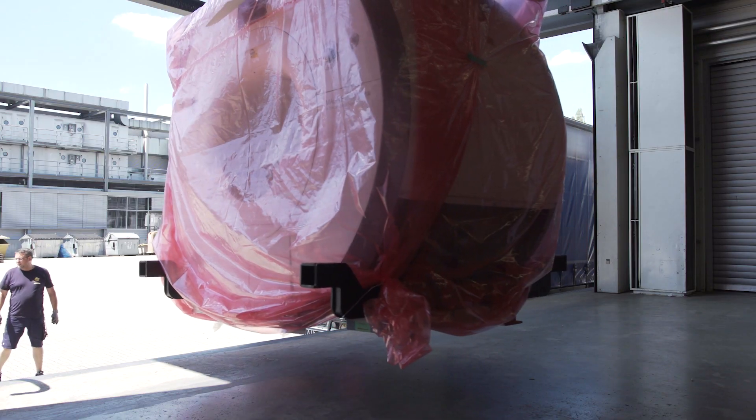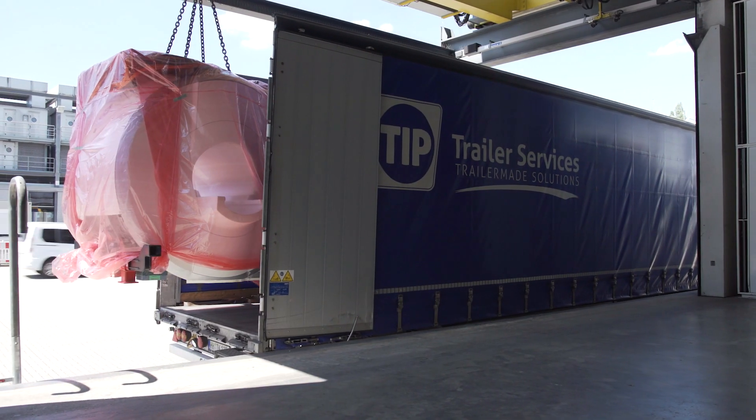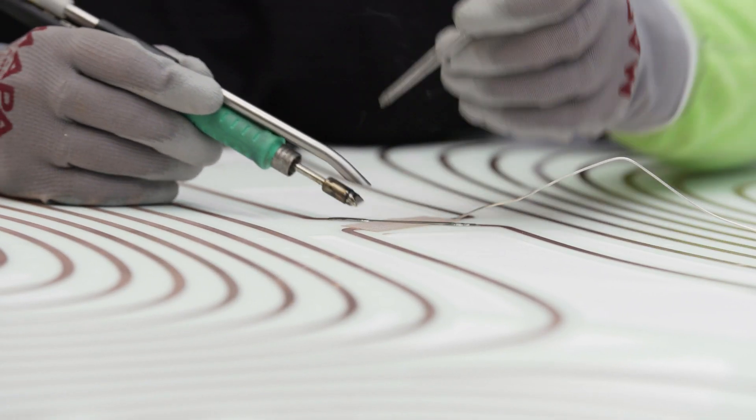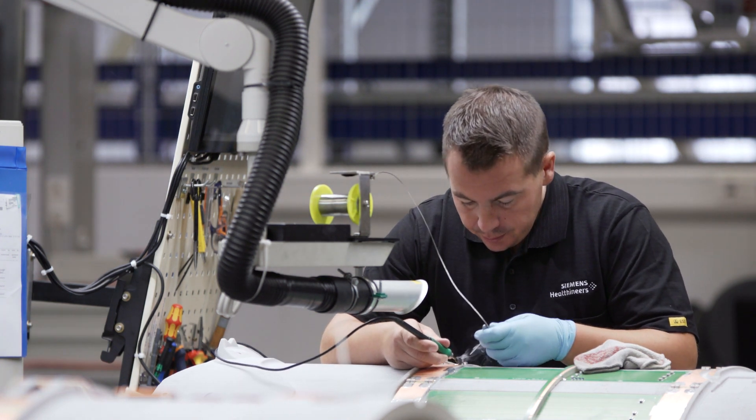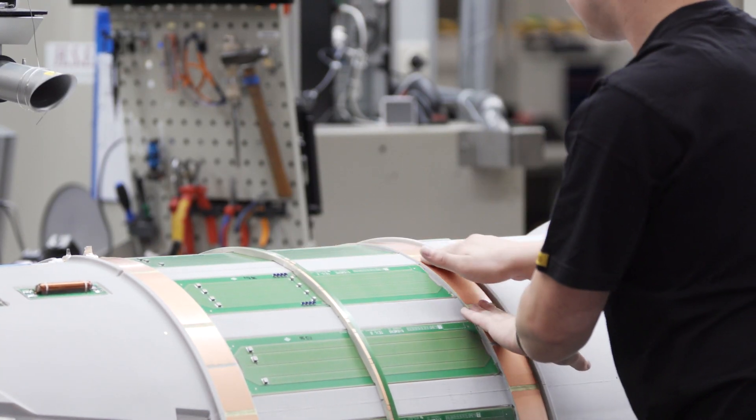The effort to install a magnet in a common building can get very, very complicated. You have to do a lot of planning and preparation before you can enter with a magnet and the system into the building. With our new product this is getting much, much easier — because you don't have to consider a quench pipe connection, helium filling, a magnet power supply, or a number of other things which are now simply gone.